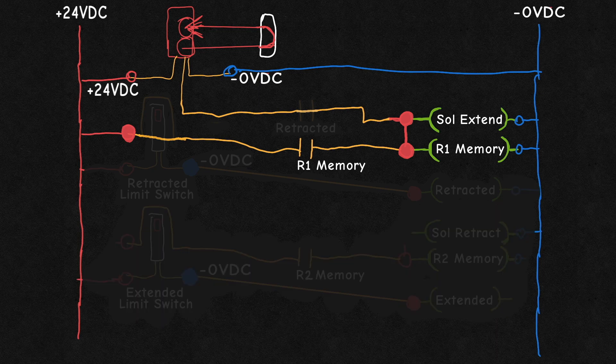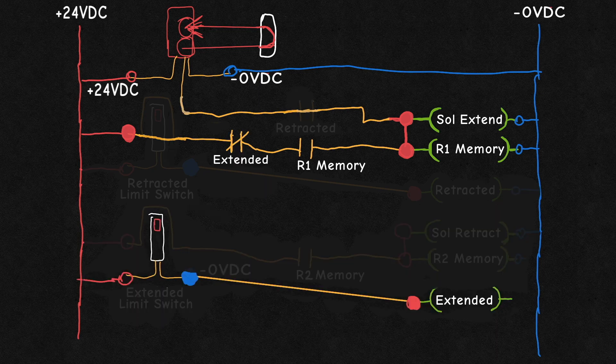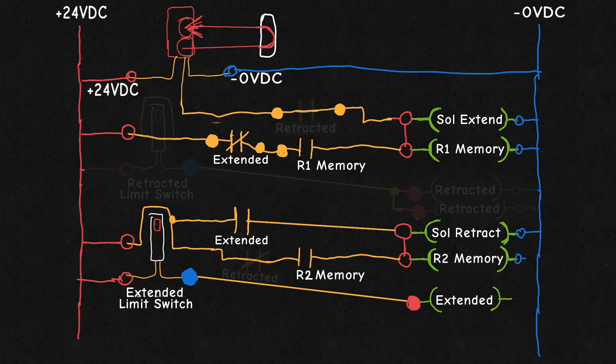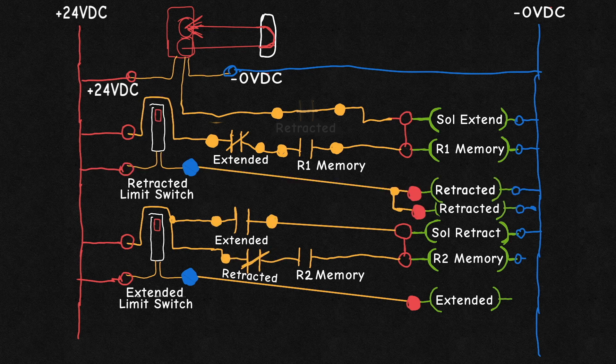We need the solenoid to be deactivated upon reaching its destination. For that, we add a normally closed contact in series with the memory circuit, which is activated by the extended sensor. This way, when the cylinder is extended, that circuit can be deactivated. Now, because this cylinder requires being driven in both directions, we then have to activate the retract solenoid. Using the same relay's normally open contact, we can use another memory circuit to activate and maintain that solenoid until it reaches the retracted position again.